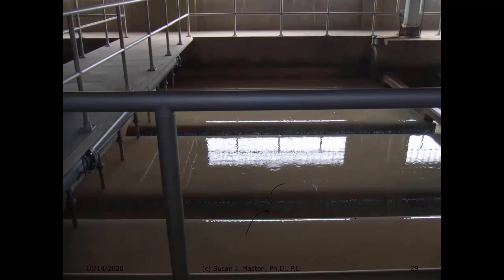Because it's a groundwater plant, they are able to recycle this water to the headworks of the plant in order to capture that calcium carbonate precipitate again. So it basically goes through the whole plant all over again, to try and capture it a second or third time, and also to use the excess calcium hydroxide in there to help raise the pH.